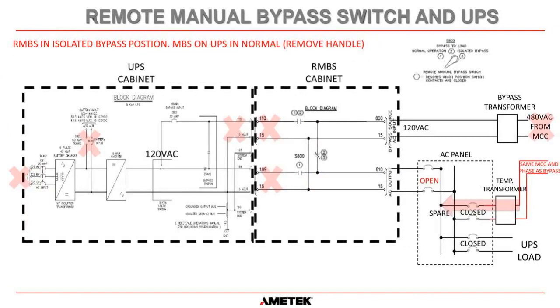So now what we can do is install the remote manual bypass switch cabinet, okay? And hopefully you have done your pre-planning and you've already mounted it to the wall. You've already run the conduit between the RMBS cabinet and the UPS cabinet in preparation for connecting it. The important thing is that when you install the RMBS, we want the switch to be in the isolated bypass position, which is position number 3, okay, which means this contact here is open. You can see that says 1 and 2, that says 1. This one here says 3, so that is the only contact that's closed, because that means that we're going to have no power at these points here, okay?